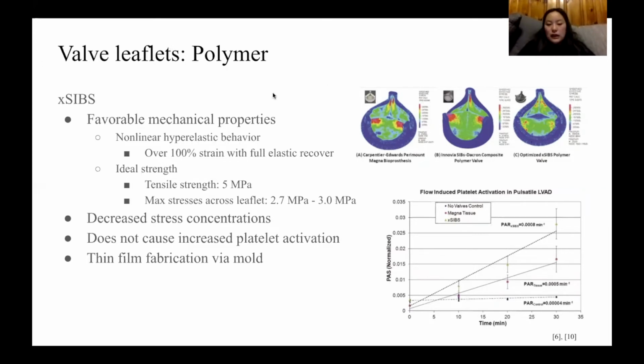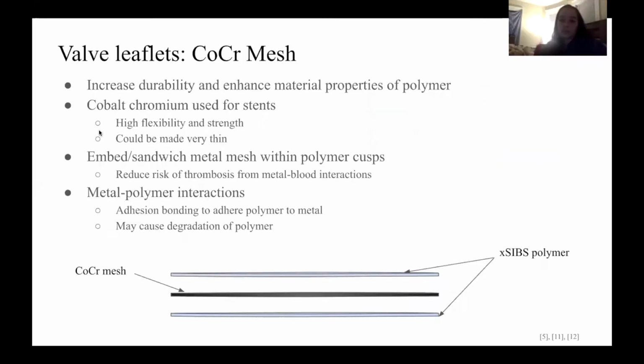In one study, as seen in the graph on the right, based on hydrodynamics testing using DTE, it did not appear to cause a significant increase in platelet activation that would cause thrombosis when compared to regular tissue valves. Our device has a cobalt chromium mesh embedded within the polymer to enhance the durability. As discussed earlier, cobalt chromium can be made very thin and retain its strength.